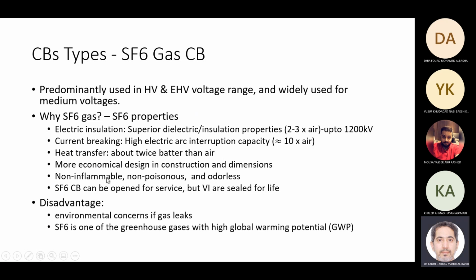However, it can also be opened. You can open an SF6 breaker for maintenance, but you cannot open, let's say, a vacuum tube. What is a disadvantage is the concern of SF6 with regards to greenhouse gases. SF6 is one of the greenhouse gases, and it causes global warming, and that's why there is now an advancement in looking for a replacement for SF6. There are mixtures of gases, and other types of gases are now being tested to replace SF6.